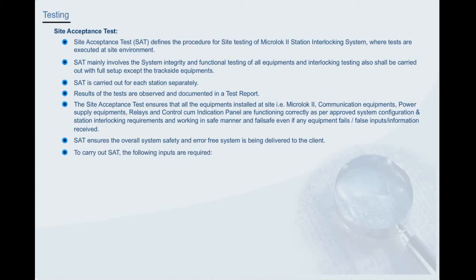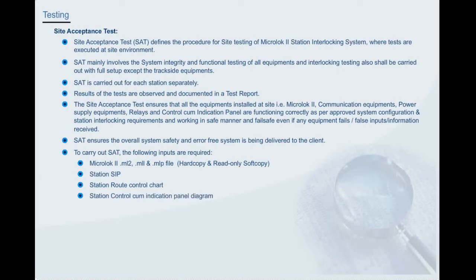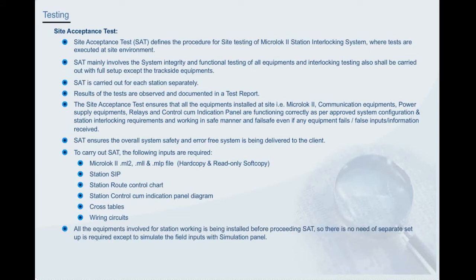To carry out site acceptance test, the following inputs are required: Microlok II .ml2, .mll and .mlp file, hard copy and read-only soft copy, station signal interlocking plan, station route control chart, station control cum indication panel diagram, cross tables, wiring circuits. All the equipment involved for station working is being installed before proceeding for site acceptance test. So, no separate setup is required except to simulate the field inputs with simulation panel.